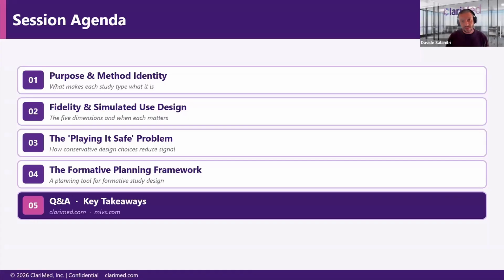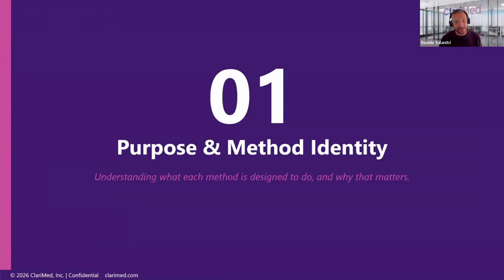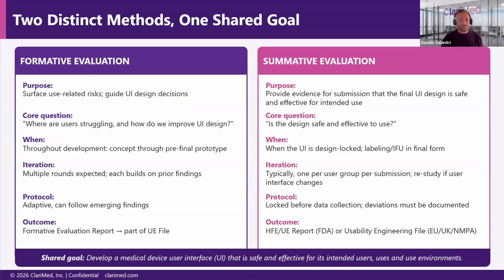And this is one of the main reasons we're having this chat: more and more, and Denise can confirm that, clients come to us and they say, we want to do a formative. And we say, well, that's perfect. Great. How do you want to do it? Exactly like a summative. And we are like, okay, here there is an issue. How do you want to do a formative exactly like a summative? There are two different things. Doing the same thing twice is not very smart if you are developing your device.